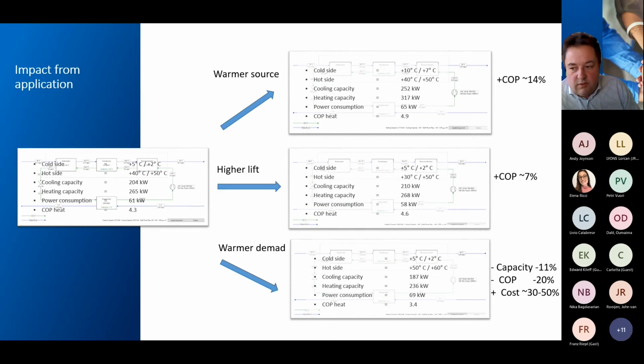But in cases where you could get a higher pinch, or you could design your system with a higher pinch than 10 degrees, going up to 20, there's also a COP improvement. And then the last thing is, had we, instead of what was chosen by the design engineers, chosen 60 to 50 instead of 50 to 40 in this case, the COP would actually have dropped 20%, and we would not have achieved the surplus energy production of the building.